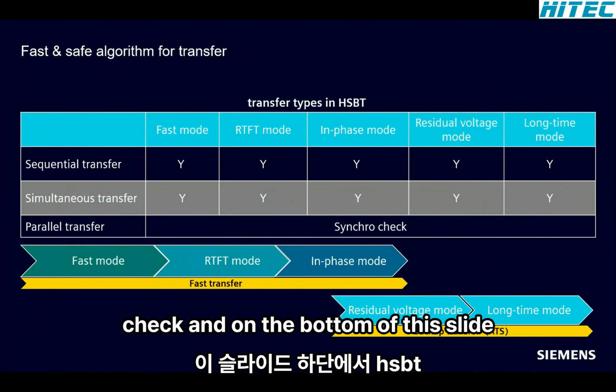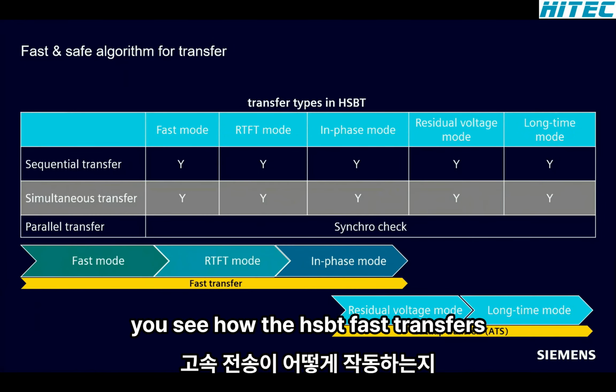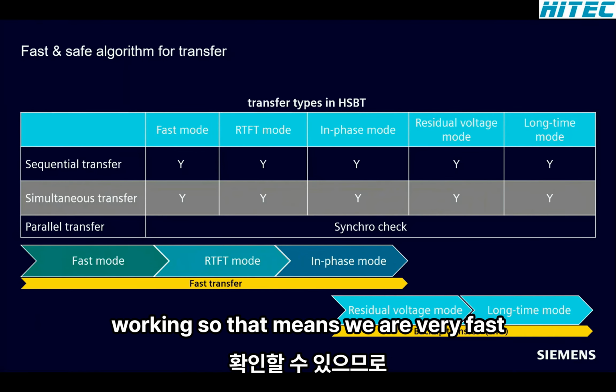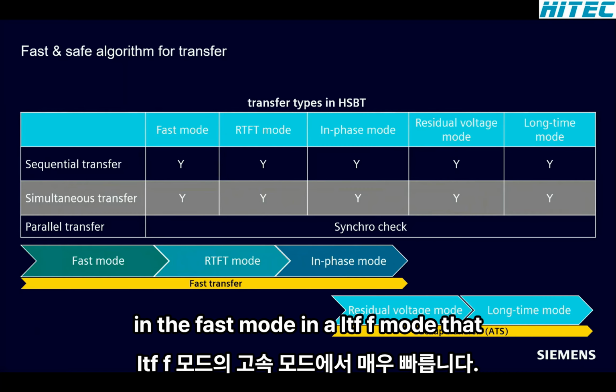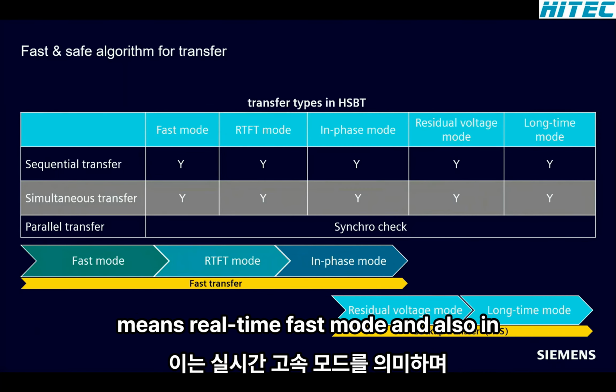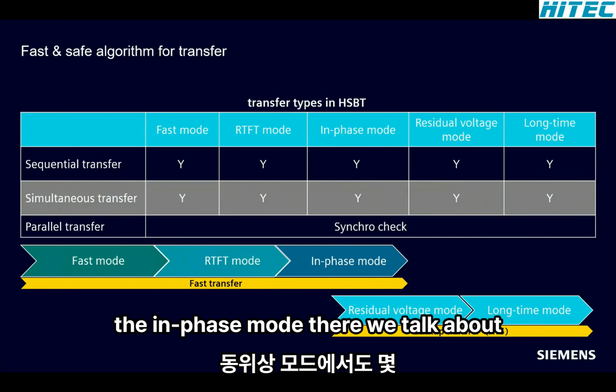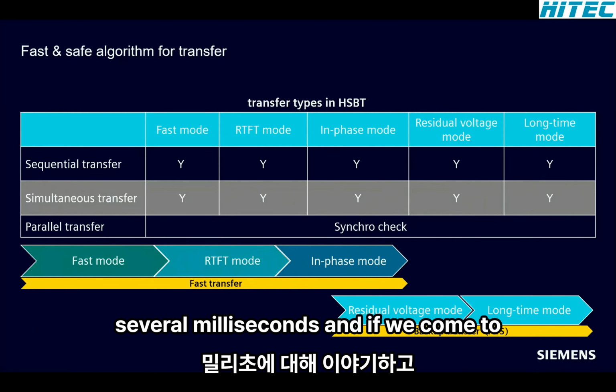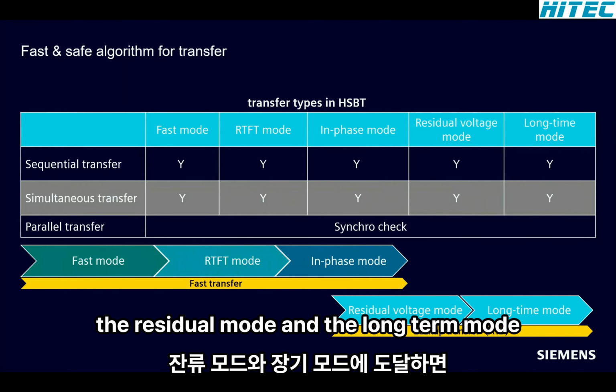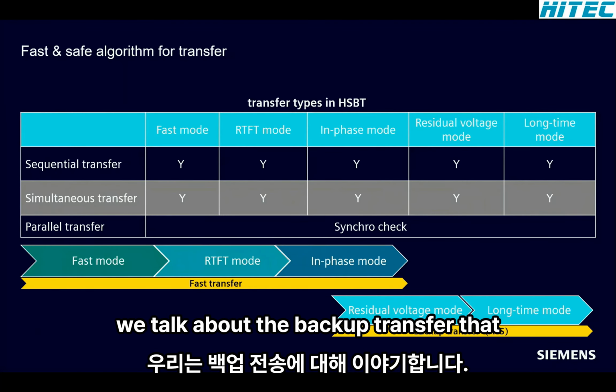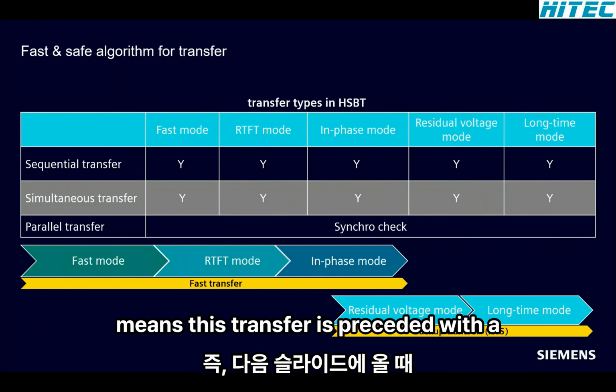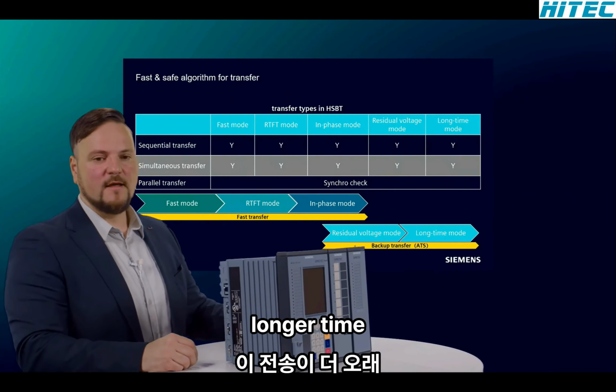And on the bottom of this slide, you see how the HSBT fast transfer is working. So that means we are very fast in the fast mode, in the RTFT mode, that means real-time fast mode, and also in the in-phase mode. There we talk about several milliseconds. And if we come to the residual mode and the long-term mode, we talk about the backup transfer. That means this transfer is proceeded with a longer time.